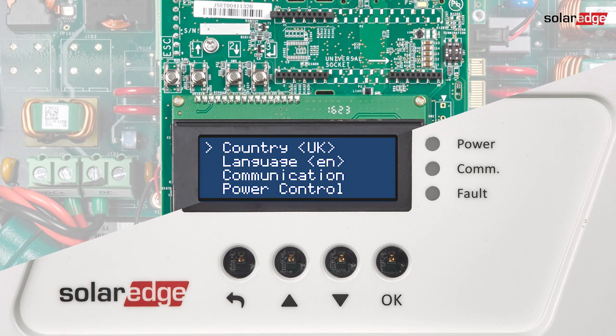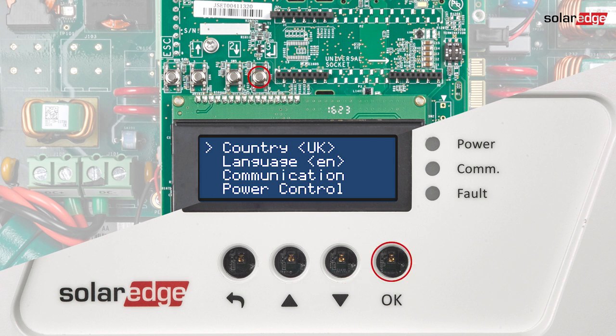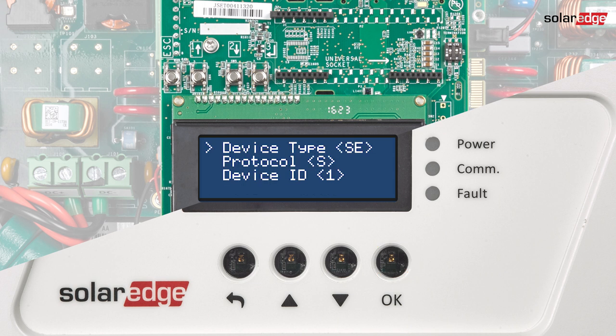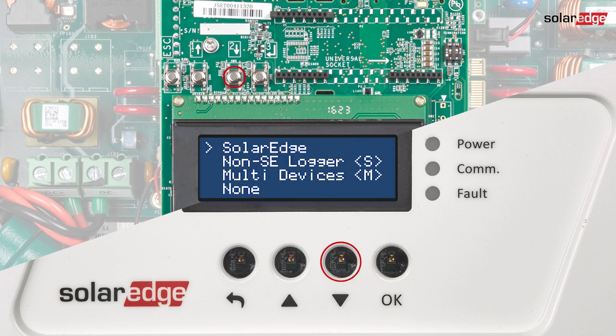We now enter the inverter configuration menu. Use the up and down buttons to scroll and the OK or Enter button to make a selection. Select Communication — we will now configure the RS-485 bus. Select RS-485-1-conf and then select Device Type; set it to multi-devices.